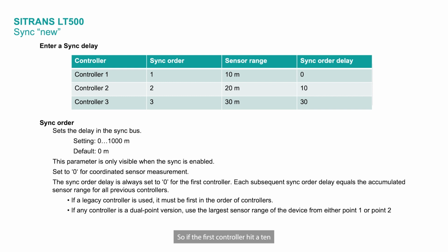So if the first controller had a 10-meter range, you would enter a 10-meter delay on controller 2. And then any subsequent controllers, we need to enter the sum of all of those delays. So if we have a 20-meter range on controller 2 and a 10-meter range on controller 1, we need to enter a 30-meter delay on controller 3, and so on, to ensure that we fire and read on each sensor before the next sensor does its measurement cycle.